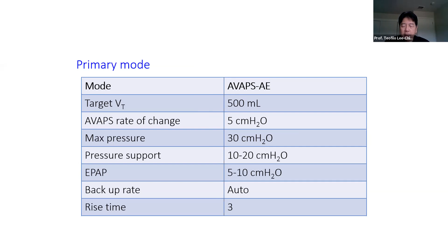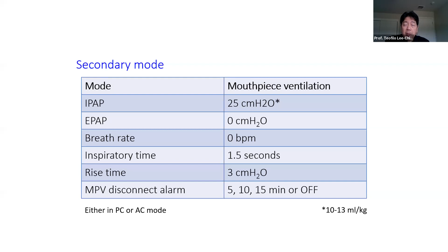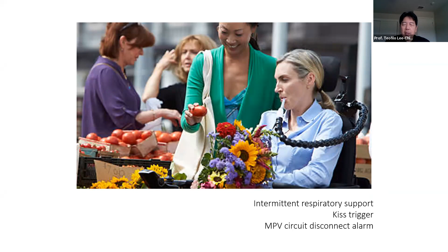You could plan for a secondary mode, such as a mouthpiece ventilation. Why? Because in the chronic setting, patients are able sometimes to leave the bed and bedroom. So when you have a mouthpiece ventilation, this provides an intermittent support rather than continuous. The trigger is a kiss. So the patient would turn the head and either touch his or her lips or tongue to the trigger, and the breath will be delivered. And then finally, the alarm for disconnect will be disabled.